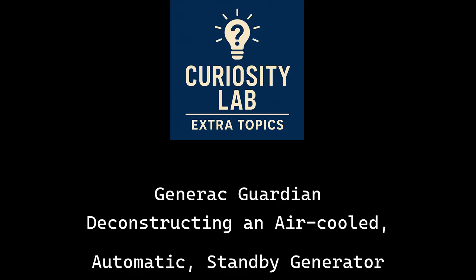Let's step back down the power curve and look at the smaller engines. Right, let's analyze the 10 kilowatt and 7 kilowatt units. The 10 kilowatt is powered by the GT530, which is still a V-twin, but it's a smaller mid-range package. And the first big difference I see from the GT990 is the oil pump. This one uses something called a gerotor system.